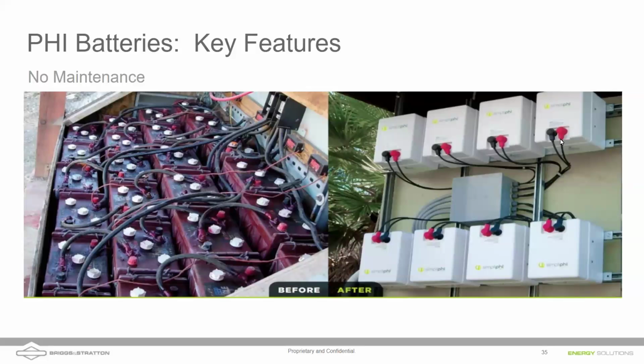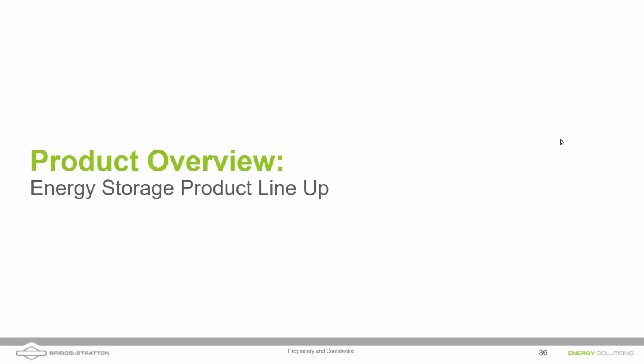Mike is asking about his 3.8s and a grid-tied system set up to supply backup loads for some small critical loads. They do a mini absorb cycle, 10 minutes at 54.5 volts daily, then the voltage decays until the next day's charge cycle, typically dropping to about 53.8 before recharging. His question is whether he's reducing battery life by not cycling them more vigorously, meaning discharging and charging more. He's asked before but is a little concerned by what he's hearing today. He also notes his Coulomb counter shunt seldom shows state of charge less than 99%.